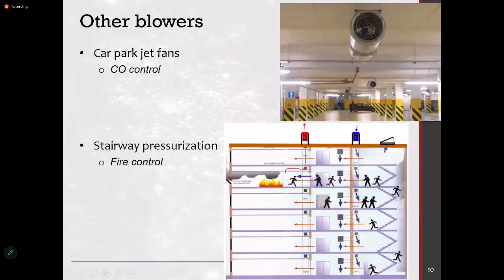So those are exhaust use. So these are other blower types. So these are called jet fans. So this is mainly for car park ventilation systems. You generally don't duct inside car parks. So you actually take it to a corner through these jet fans. So they are high RPM fans where you can blow the air over a certain corner and take it out from that point.